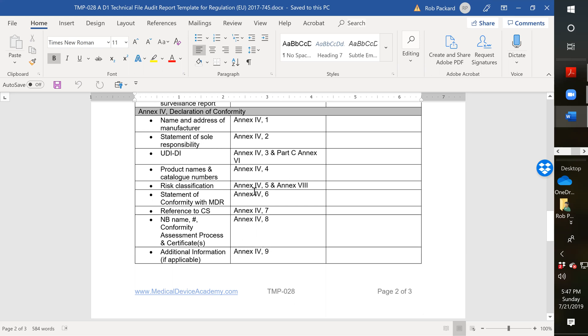They haven't all changed, so it's possible that they aren't updated, but at least it should not say Annex 9. It should say Annex 8. There should be a statement of conformity with the MDR instead of the MDD. They may reference common specifications, so that's one of the things you might want to look at first to see, have they identified any common specifications in their declaration of conformity before you go in to the rest of the technical file.